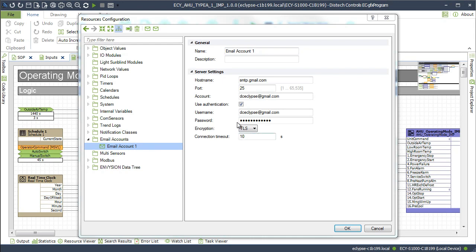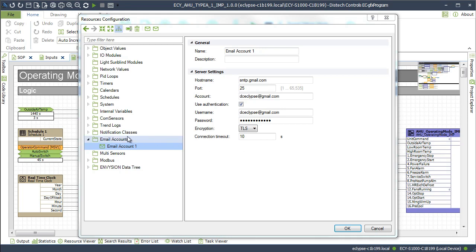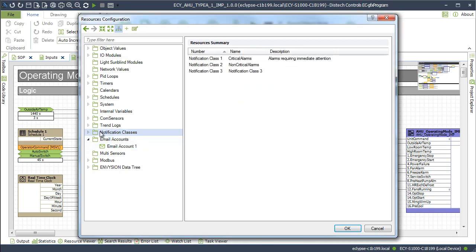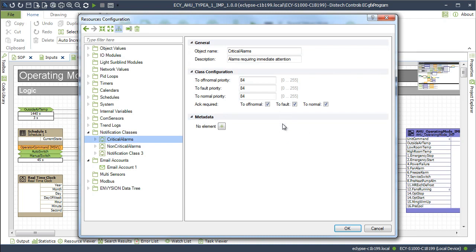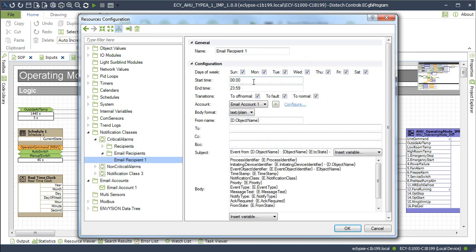Alarm notifications can now be sent by email. The configuration of the email notification settings are made in EC-gfxProgram. The resource configuration window now has new configuration tree items that are used to configure email notifications such as email accounts and notification classes. The email title and body text use plain or HTML text. Variables based on BACnet notification objects properties can be inserted.